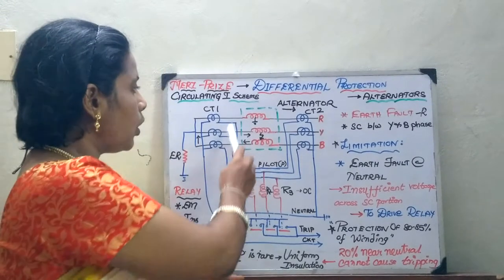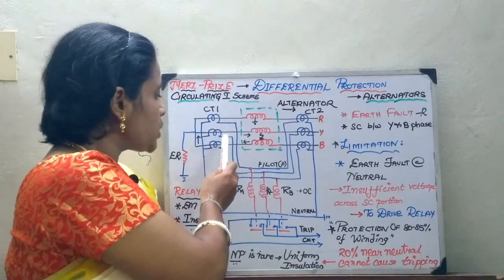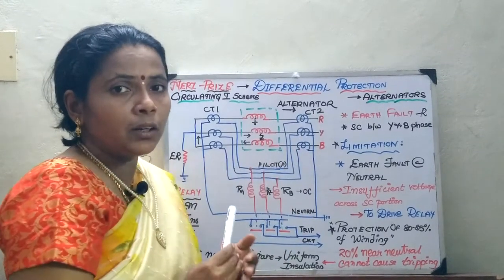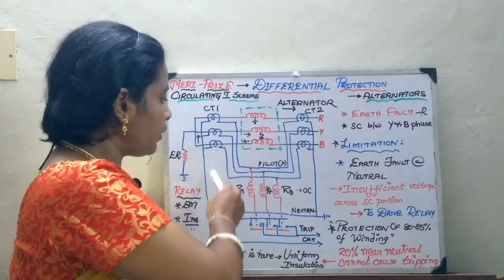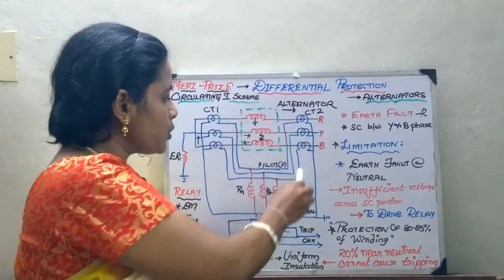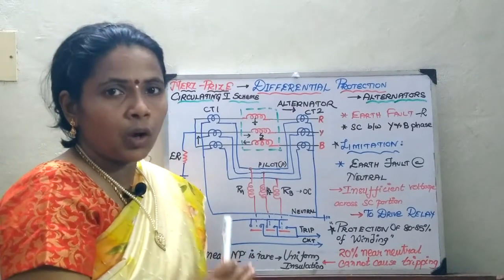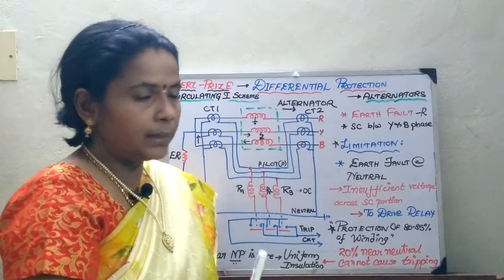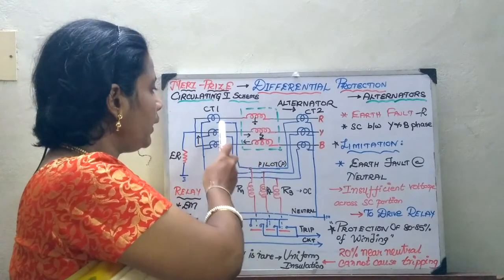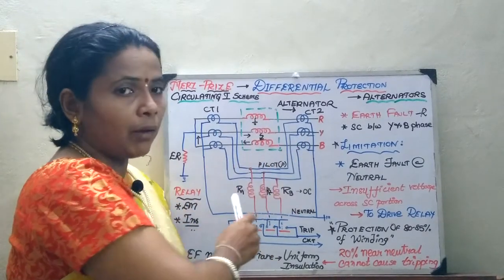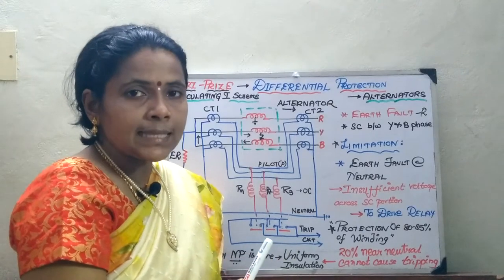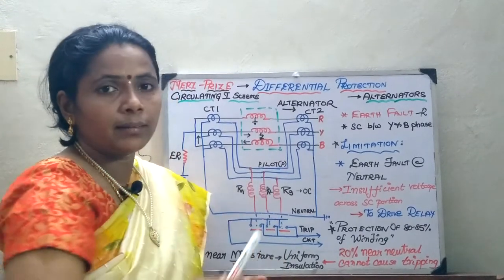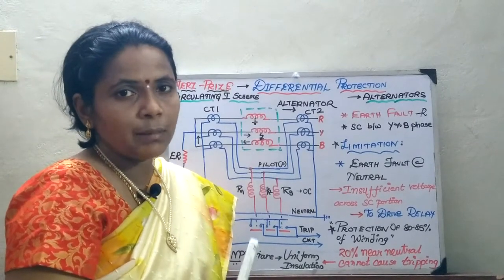This is the alternator winding to be protected, and CTs are connected on either side. Under normal condition, when there is no fault, the current entering the relay coil will be balanced and the relay will not operate. Once a fault occurs at any point, the current through the relay will be unbalanced, and this differential current is going to operate the relay. This is the base concept.